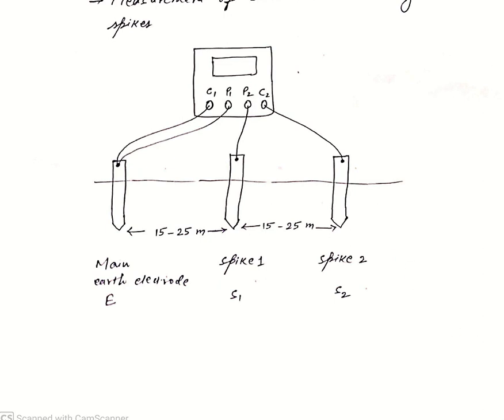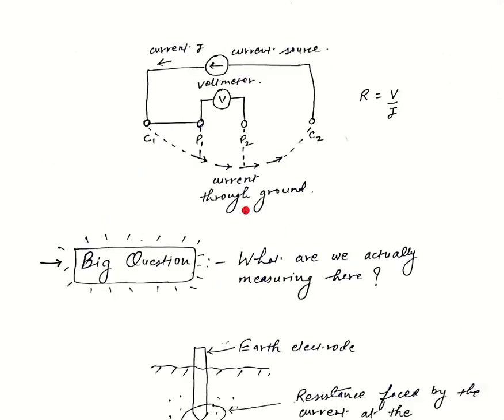If we look at the circuit diagram of the instrument, we see that C1 and C2 are connected with the current source and P1 and P2 are connected with the voltmeter. There is a fixed amount of current that flows through the source, then through C1, then through the ground and then to C2.